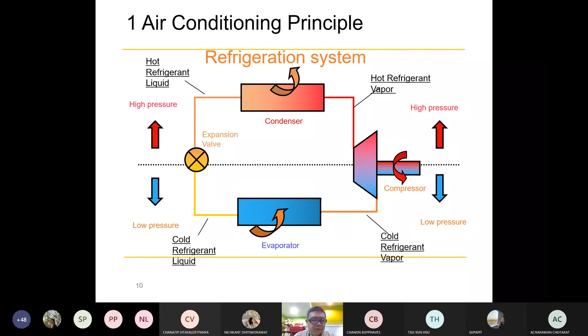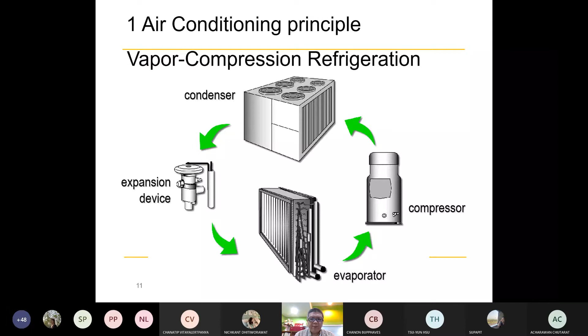The compressor will look like this, and the condenser will be air cooled. This one is an air cooled condenser, and the expansion valve device is actually like piping, which reduces the pressure, and the evaporator is the coil. This is the basic refrigeration system, which is the same as the previous one. Okay, so this one will show you more graphically.